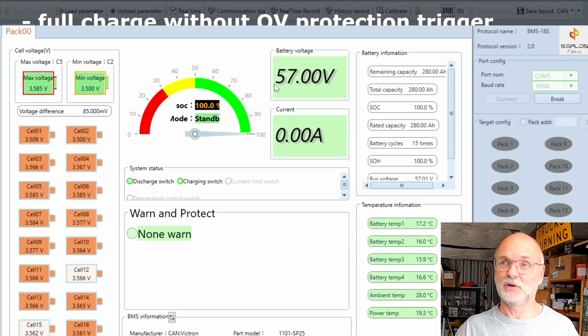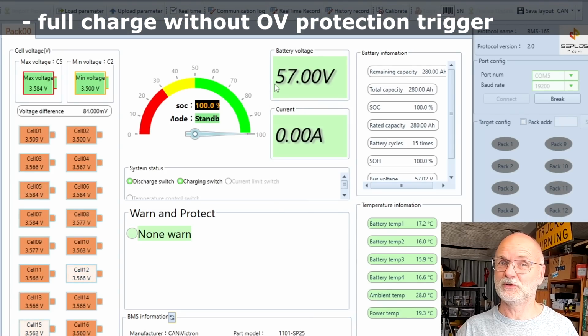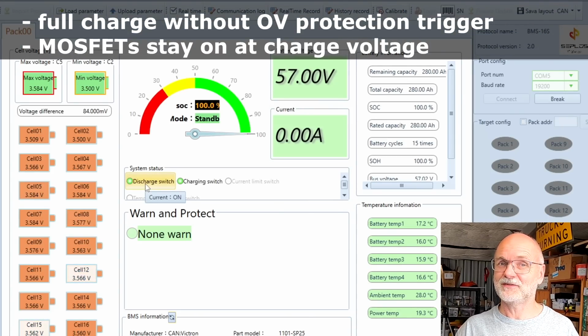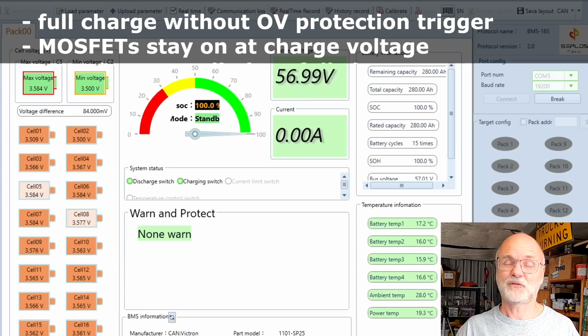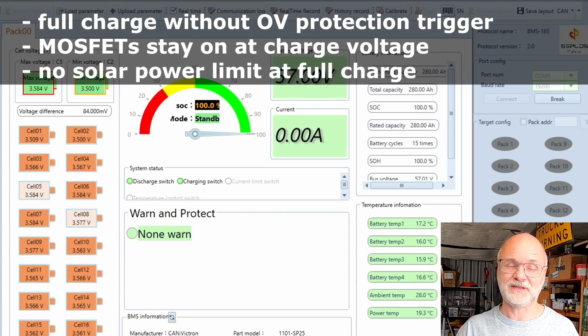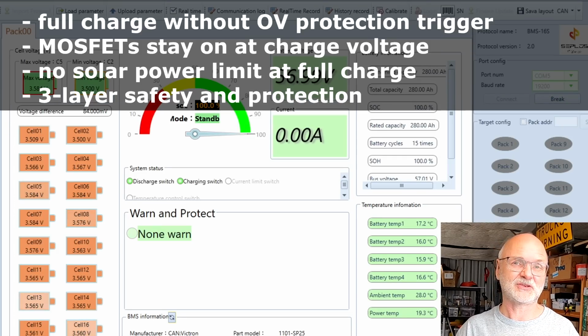We can charge to a voltage which is not the protection voltage. We keep the charge and discharge MOSFETs turned on. We've got no limits for my MPPTs, even when the battery is fully charged. And we now have a 3-step protection system in the BMS, which is great.